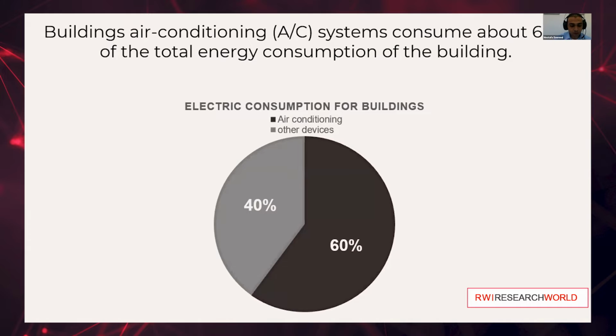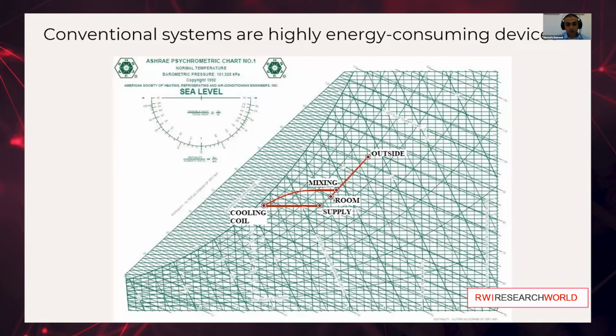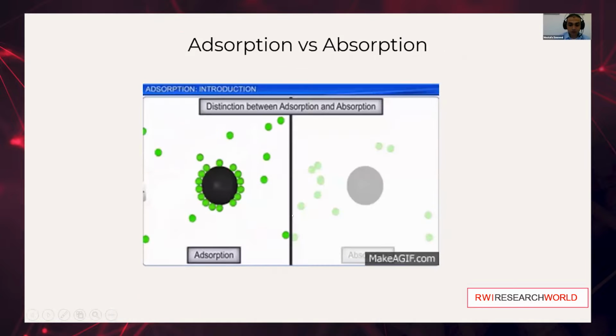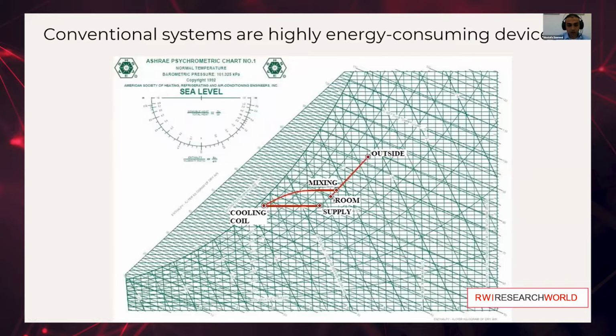energy. In hot humid regions where the outside latent load is high, conventional air handling unit systems are used. Fresh air at ambient conditions is mixed with the return air from the room in a ratio that keeps the required fresh air for the space. Then this mixed air is cooled and dehumidified after going through a cooling coil. However, after cooling and dehumidification, the air undergoes sensible reheat in order to be adjusted to the supply conditions of the room.